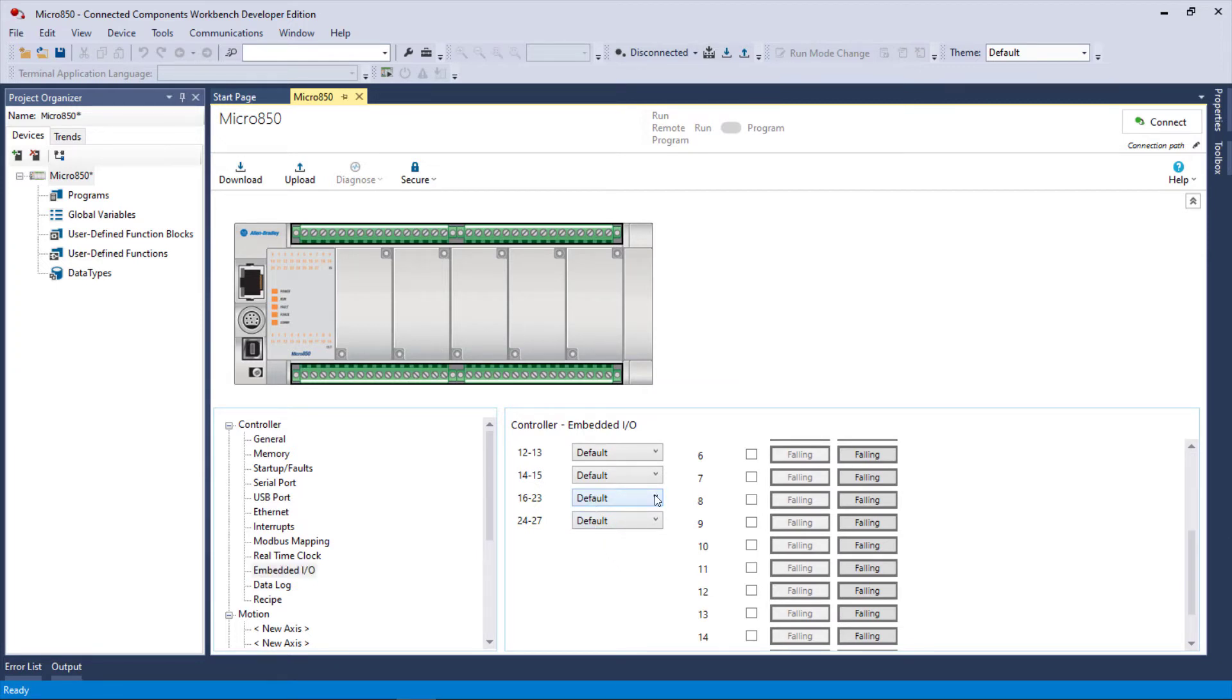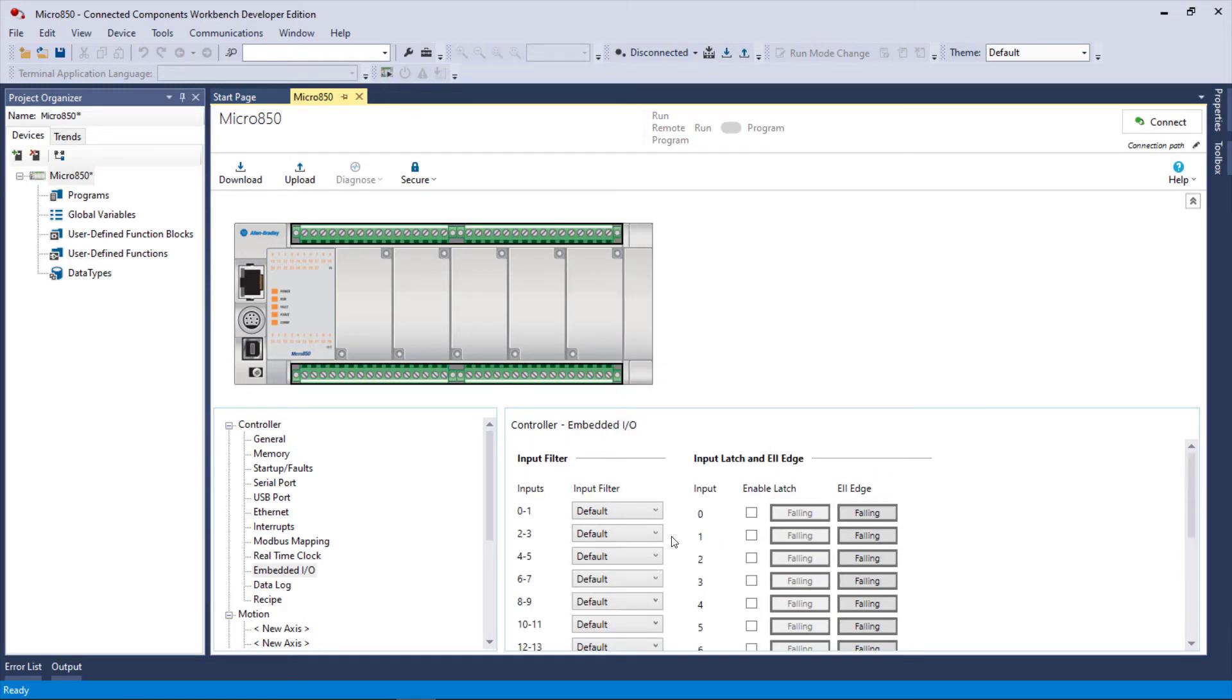If you set the filter, that's going to do inputs 16, 17, 18, 19, 20, 21, 22, 23. That's eight inputs with one filter selected. You don't have to use default. Then you can also do some latching, which is a little bit different than some of the other processors.